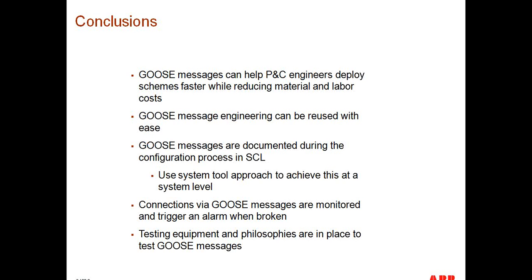So, in conclusion, Goose messages can help protection and control engineers deploy schemes faster while reducing material and labor costs. Goose message engineering can be reused with ease thanks to the Substation Configuration Language and system tool approach. Goose messages are documented during the configuration process in SCL. Use the system tool approach to achieve this at a system level.